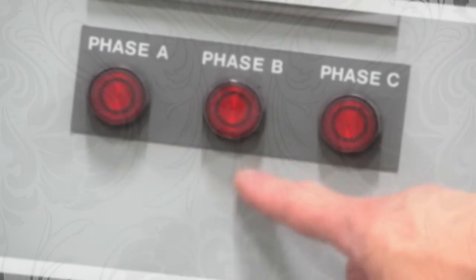Normally, when a ground fault occurs on an ungrounded system, a delta-delta system, for example, if you don't have high-resistance grounding by National Electric Code, you have to have three indicating lights: Phase A, Phase B, Phase C.